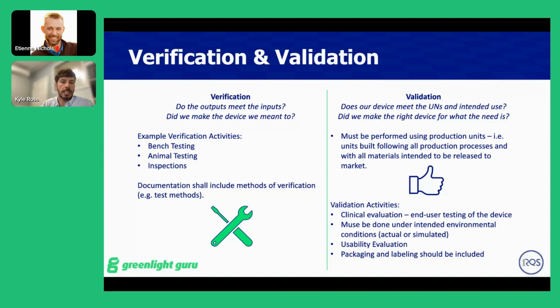Verification activities can also include external testing, so things like your biocompatibility testing, your 60601 testing, cybersecurity testing, FCC, Bluetooth, wireless connectivity, any of those things can also be part of your verification. Even though they're done externally, there should be formal protocols that are developed by the test lab and then tested for your device. Each of these should be approved, and then when verification is done, also have a design review showing that all the proper people reviewed the output of the results of your verification and signed off on these activities.